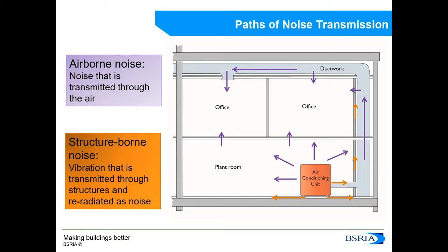There are two types of noise. Noise produced by a product transmitted through the air is called airborne noise, and sources include fans, compressors, pumps and motors. Vibration transmitted through structures and radiated as noise by connected components is called structure-borne noise. Sources of structure-borne noise include casing and ductwork and are typically harder to identify and control. A diagram on this slide shows purple arrows indicating airborne noise paths and orange arrows indicating structure-borne noise paths.